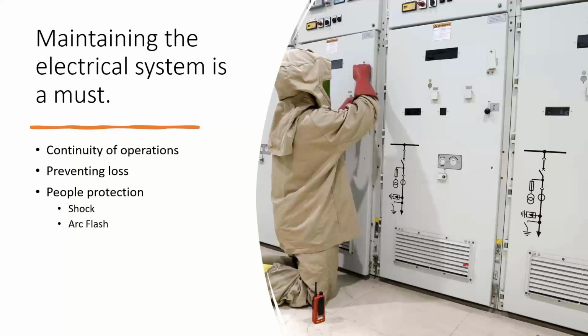Anything to add in that vein of thought? Yes, and you're exactly correct with that. So, when you're doing an arc flash study, the amount of arc flash energy that comes out of a possible arc flash is, like you said, depending on how much available fault current you have and how long that fault is lasting.